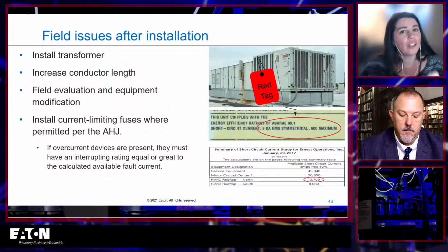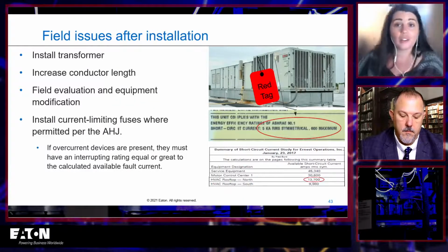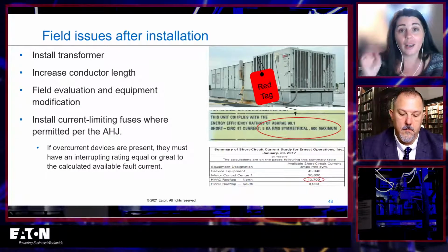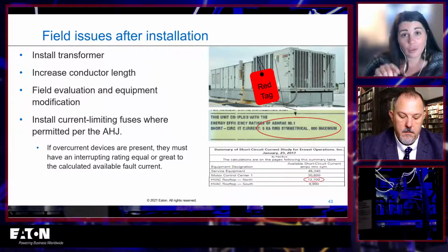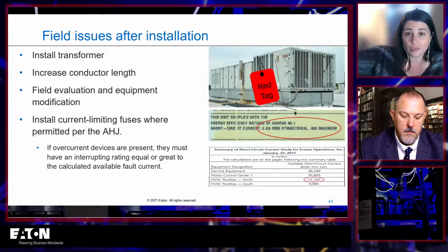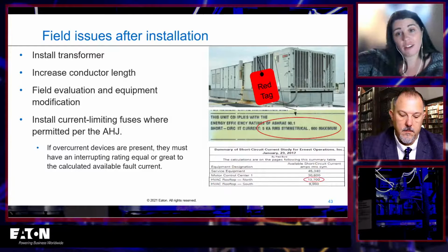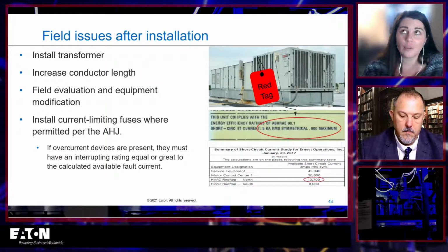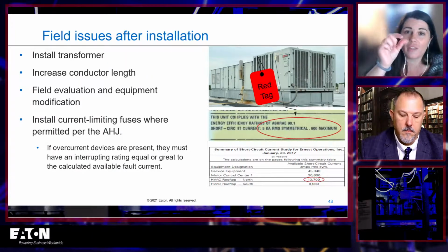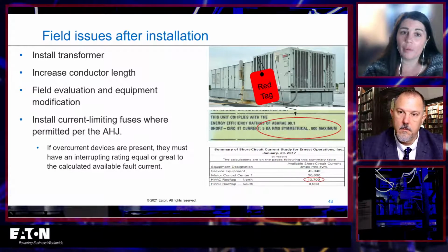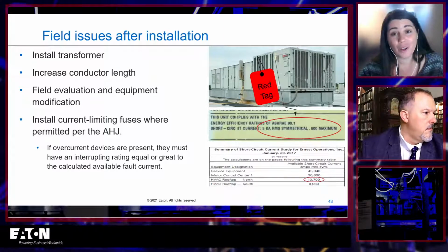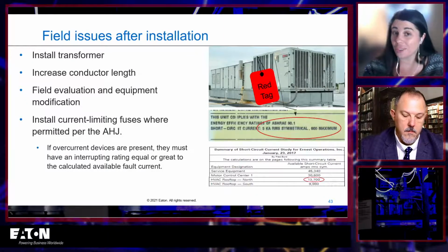And if you're really, really close and it's the difference of 5 feet of conductor could make it so that you meet this requirement, then you tell your electrical contractor when he wires it up to go up, over, and around instead of straight to it, right? But again, it really only works when you're very, very close to meeting that requirement already. And that's basically it when it comes to reducing available fault current. Those are your options, right?